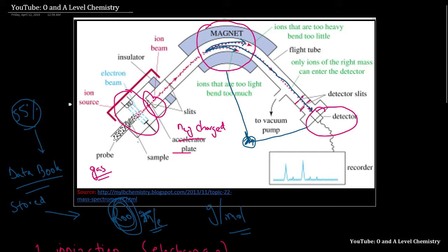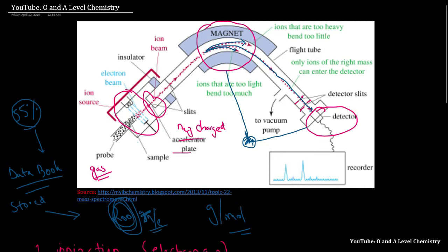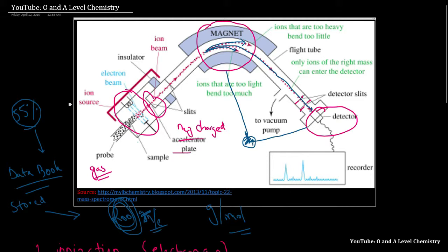Those are molecules. And if you leave air inside, your detector is going to detect those molecules as well. So you don't want that. You just want to detect your particular sample. That's why it's always a vacuum inside. If it's a vacuum inside, you cannot pump any other gas to push your sample to the detector. So the only way that your sample can travel inside the mass spectrometer is by making it positive, by ionizing your sample.